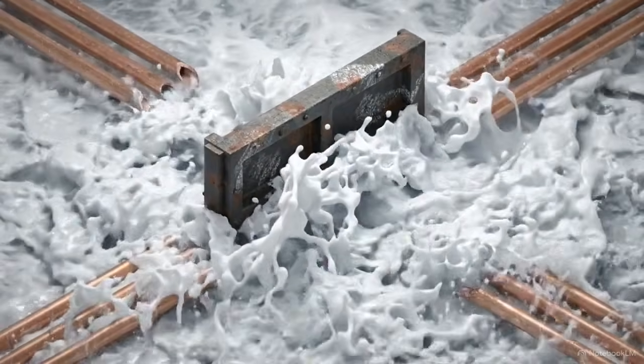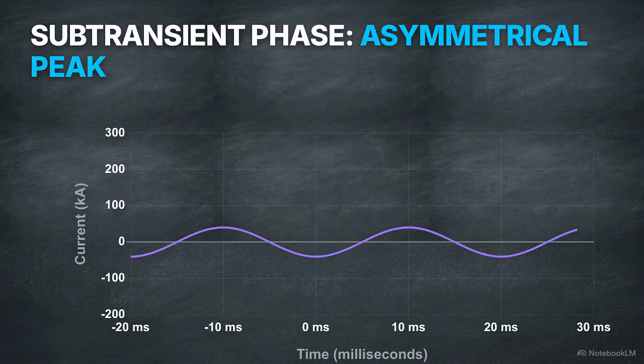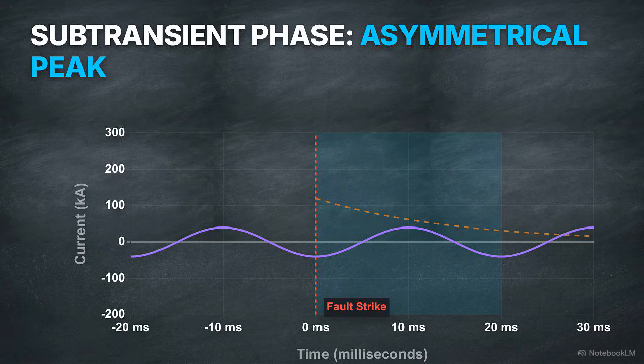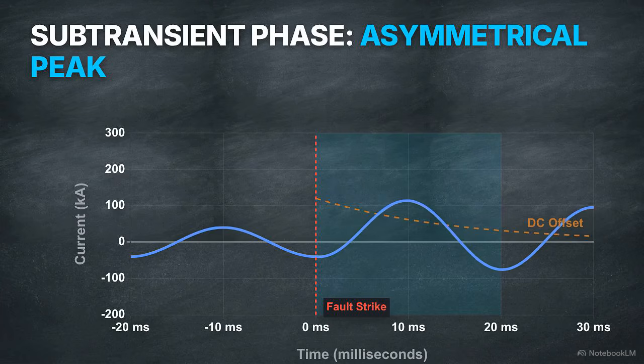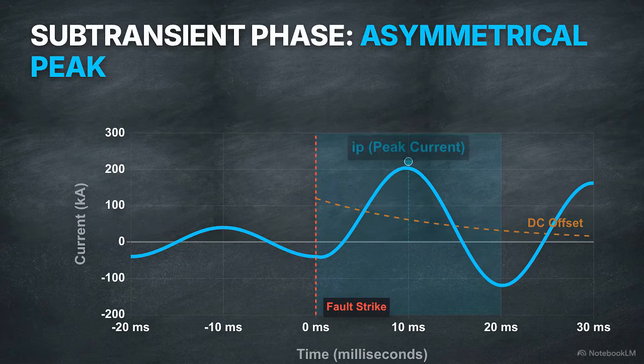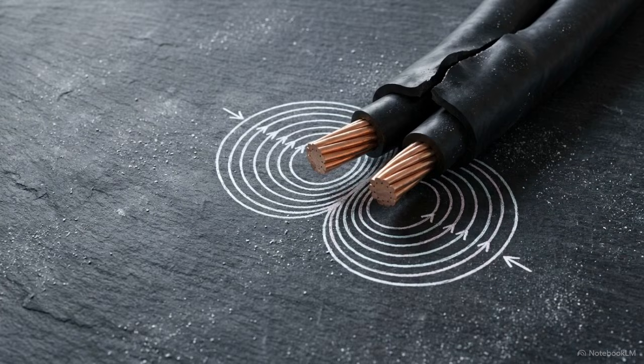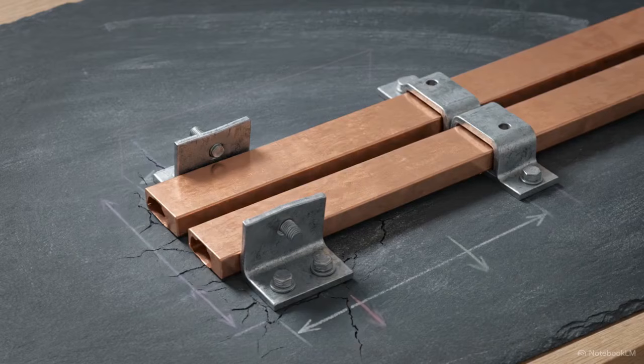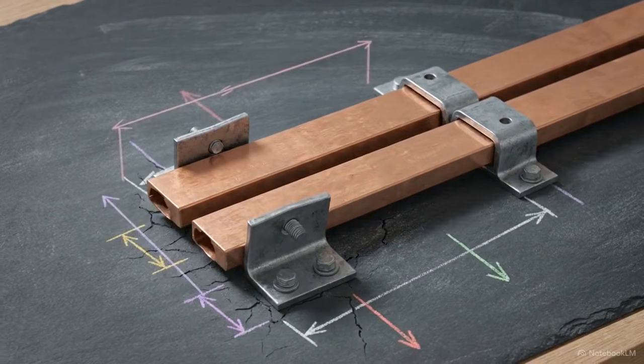Compressing our timeline down to the first 20 milliseconds, we enter the subtransient phase. Depending on when the fault strikes, the alternating current wave experiences a DC offset. The wave is forced entirely in one direction, creating a single, massive, asymmetrical peak. That sudden surge of electrons generates immense, instantaneous magnetic fields wrapping tightly around the copper and aluminum wiring. These magnetic fields manifest as extreme physical pressure.